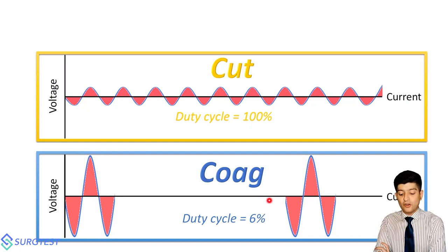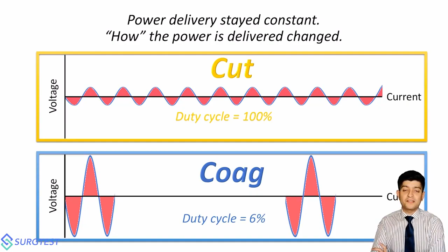Now let's compare these two forms of power delivery, cut and coag. Keeping the power setting the same at 30 watts (it could be any figure you choose), notice that the area under the curve on both sides has to remain constant. The two main differences are that on the coagulating side, the voltage is much higher and the duty cycle is lower, meaning the current is not delivered to the tissues for long periods. The power delivery has stayed constant, but how this power is delivered to the tissues has undergone significant change.